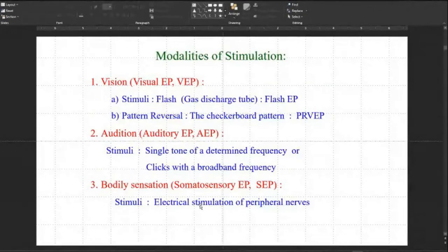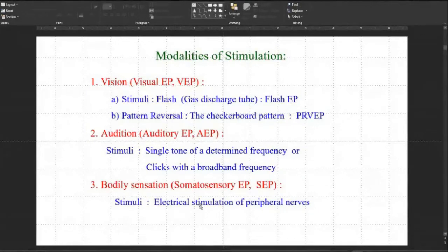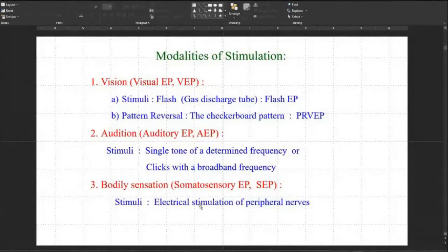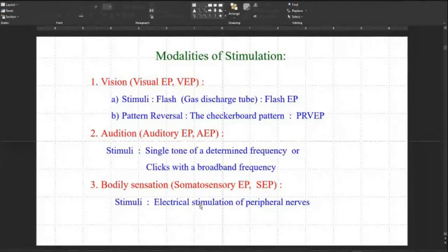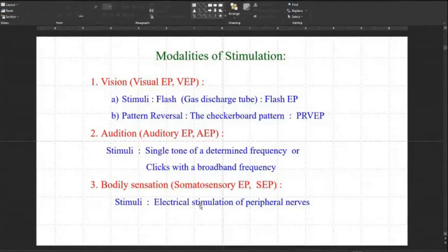Which are the modalities of stimulus? For vision — visual evoked potentials (VEP) — the stimuli are either a flash using a gas discharge tube (flash VEP), or pattern reversal, where a checkerboard pattern is displayed on a computer screen and reversed: black squares become white and white become black. This is pattern reversal VEP, generally called PRVEP. For audition — auditory evoked potentials (AEP) — a single sinusoidal tone of about 1 kHz or 2 kHz frequency, or broadband clicks (sequences of pulses), is used as stimulus.